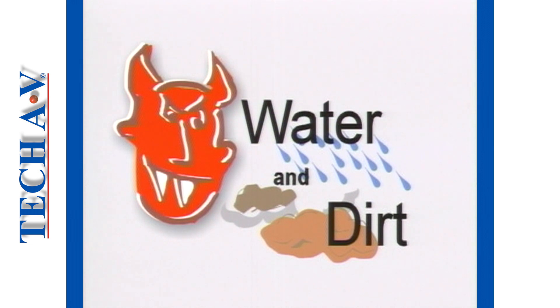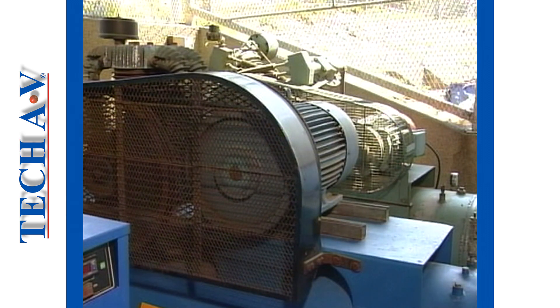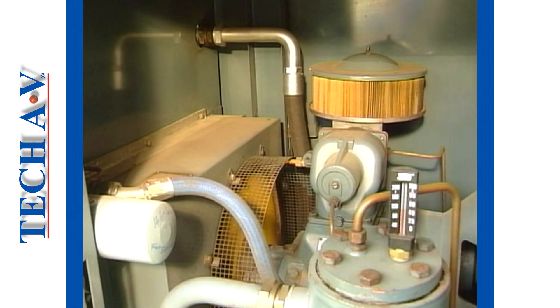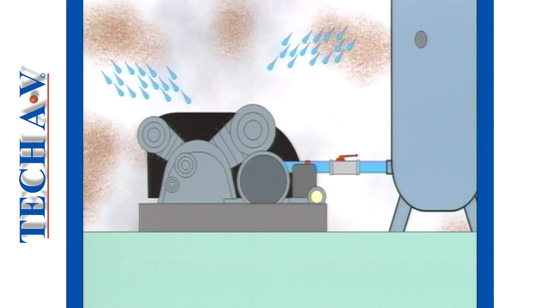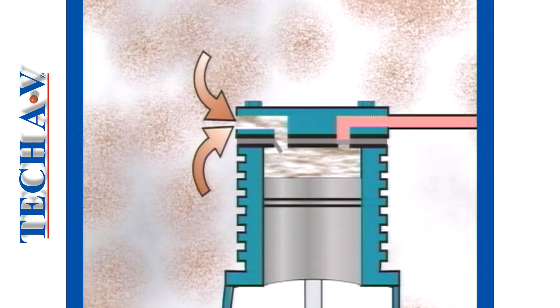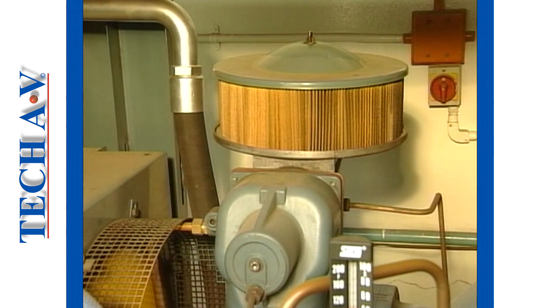There are two main problems that all compressed air systems have to cope with, and these are water and dirt, in the form of solid particles. Every compressor draws air from the atmosphere that surrounds the compressor. Unfortunately, the atmosphere is far from perfect, and in it you can be certain that there will be water vapor and dust present. These substances are harmful to the operation of both the compressor and the working units alike. Preventing dust from entering a compressor is fairly easy — we simply fit an air filter to the inlet of the compressor, and this prevents most of the dust, or solid dirt particles, from getting inside the system.